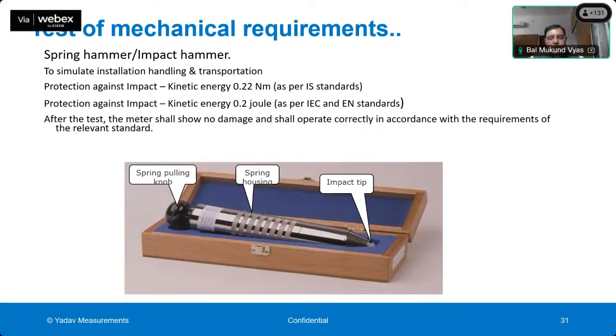This is the spring hammer. You can see a spring hammer which is specified in various standards, as per the Indian and IEC standards. The energy imparted on the meter body is 0.22 Newton meter as per the Indian standard, and 0.2 joules as per the IEC standard. The meter body and the display cover are all subjected to this type of spring impact, and it is checked that it does not cause any damage to the meter, or to the electronic circuitry inside the meter, when such an impact occurs.